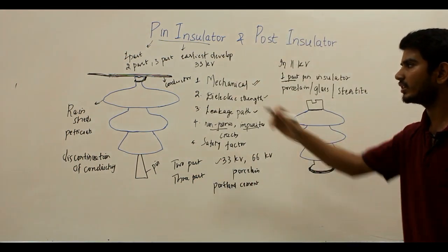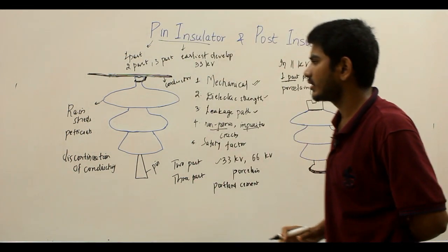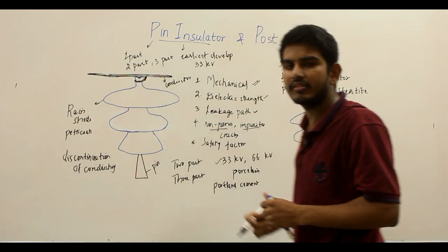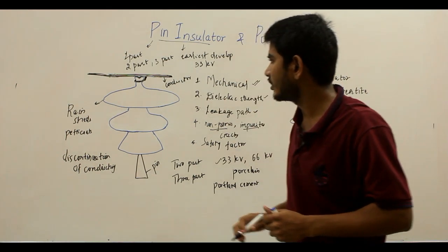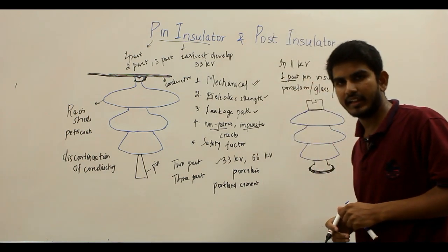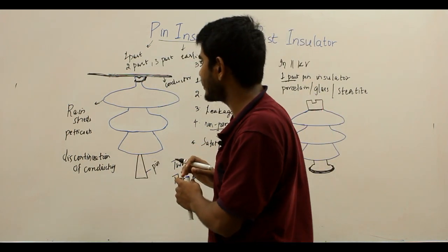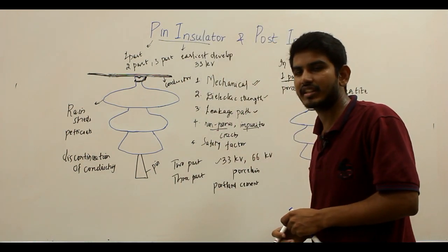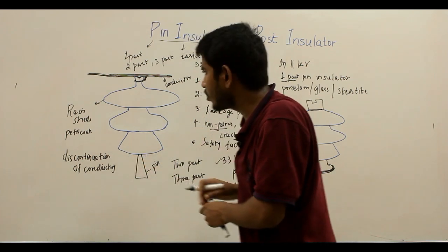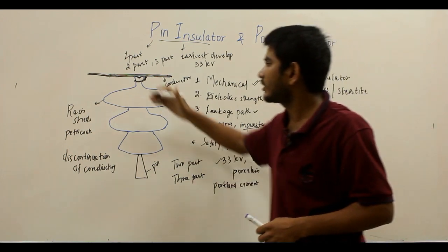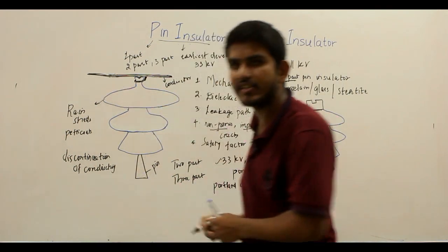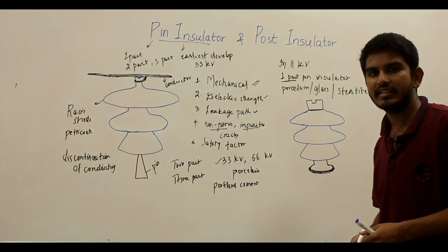Now coming to the designing of the pin insulator. As we have seen, the top end of the insulator has a groove, and this portion is your groove, and that groove houses your conductor, and the bottom end of the insulator is supported by the metallic structure which is at earth potential. So this is the live wire and this is at earth potential. Basically the insulator has to sustain the potential stresses between the live wire and the earth potential.